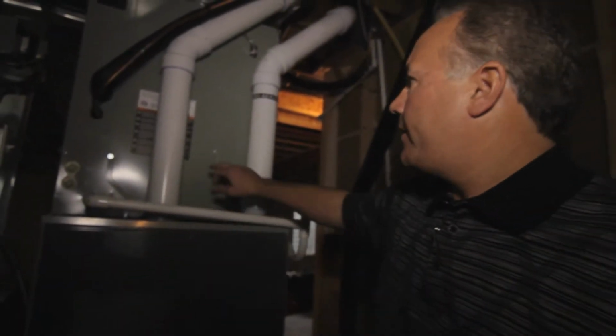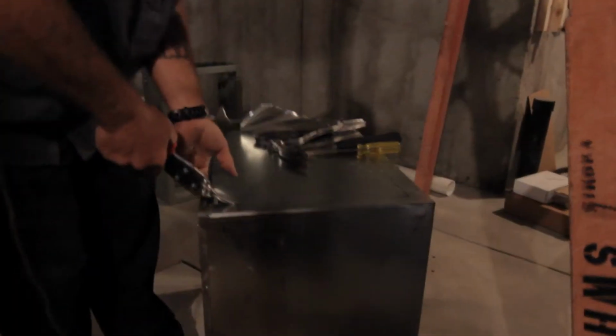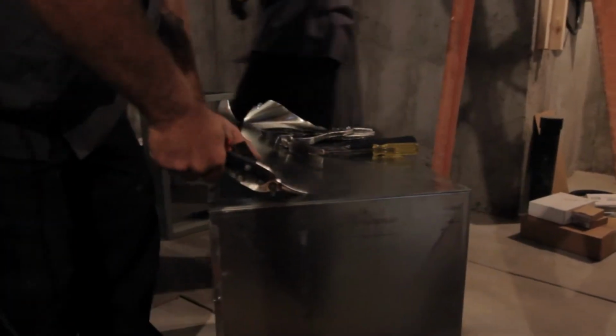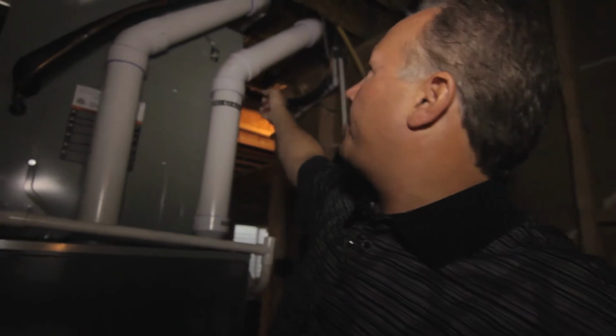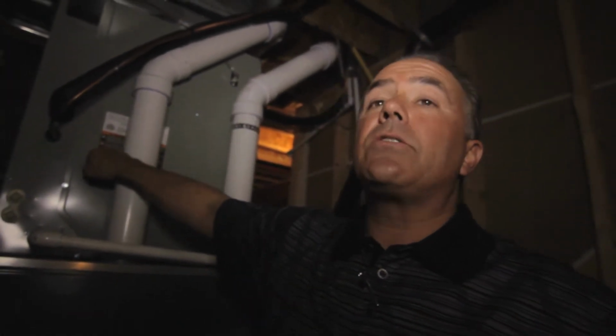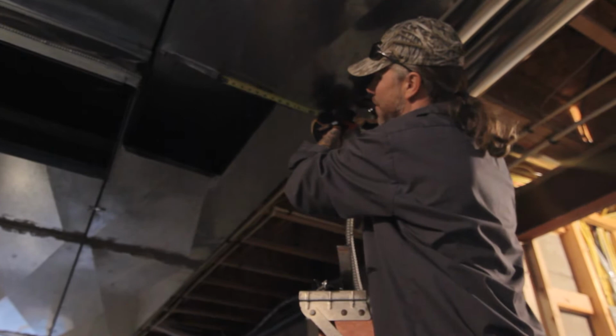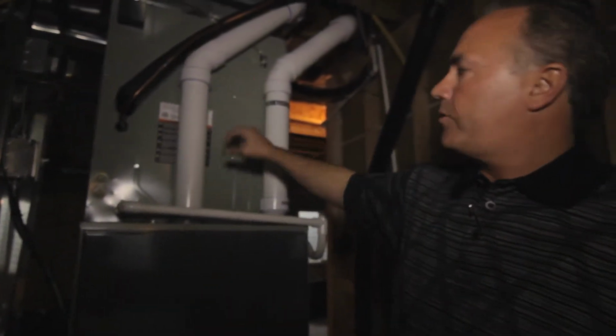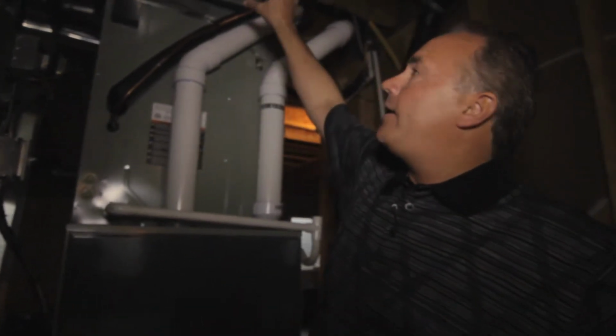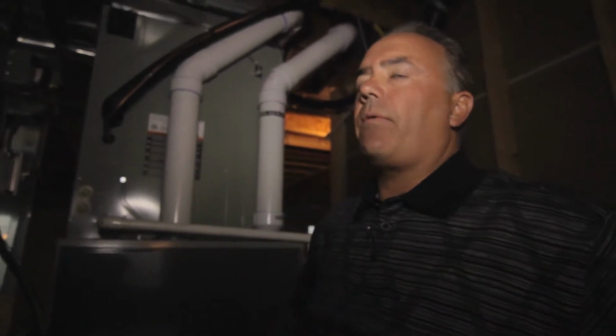It's incredible. This is your indoor cooling coil. Right in here we have an all aluminum, very important, cooling coil. The refrigerant comes from the outdoor unit, comes right in here, and goes into this cooling coil. This is what gets very, very cold. Then the blower section, which is variable speed in this furnace, comes on, runs air right up through the furnace and through this cooling coil, and that introduces the cool air into the home. So we'll look at the thermostat when we go upstairs.